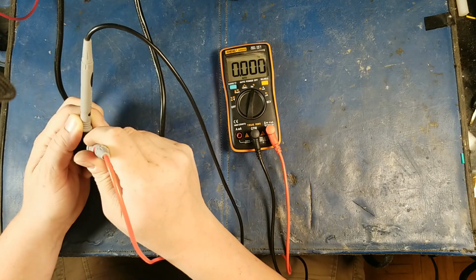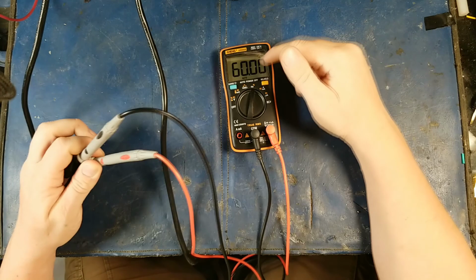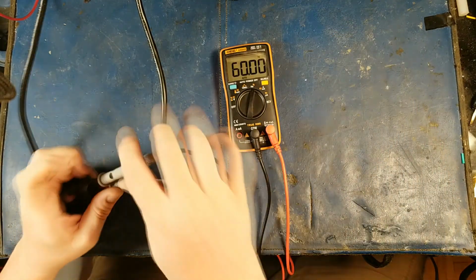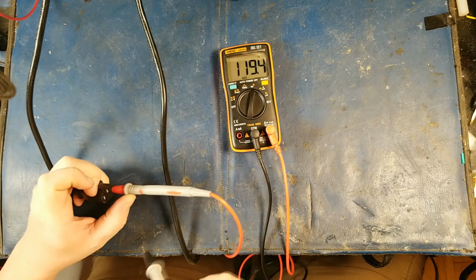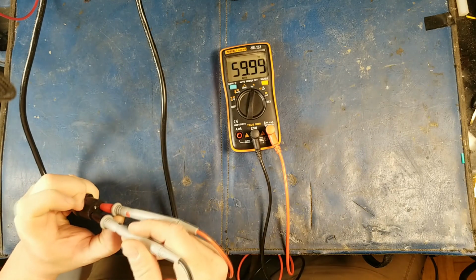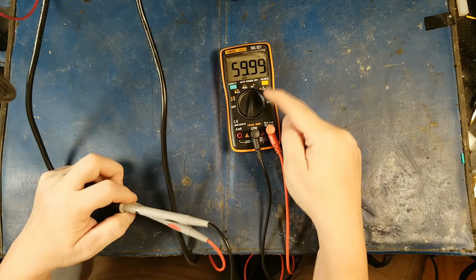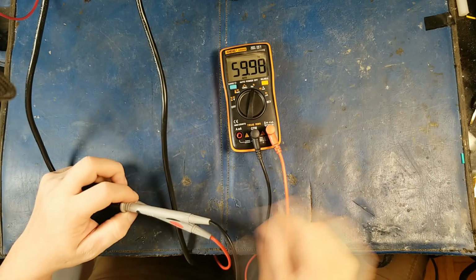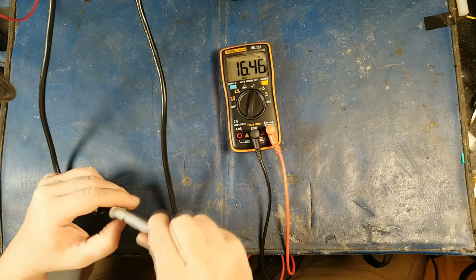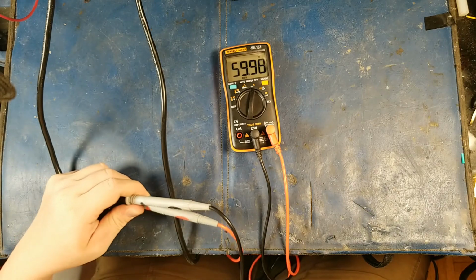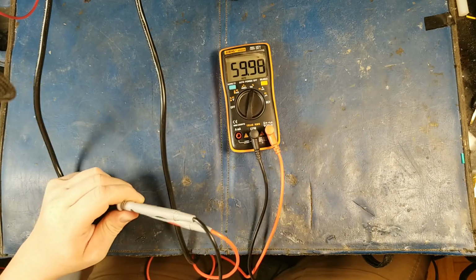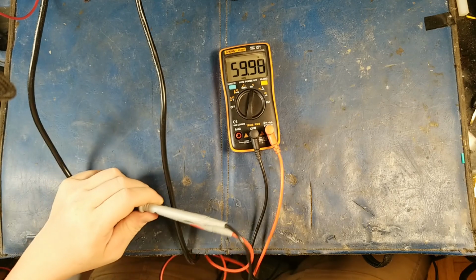Okay, if I plug this into line now, look at that, 60 hertz, bang on. You can also test it if there's no ground available, which doesn't happen very often. You can plug it into the neutral and should get the same reading. I use ground because that's a really solid reference point, typically. So there, we know we've got 60 hertz, with tolerance here plus or minus 1%.